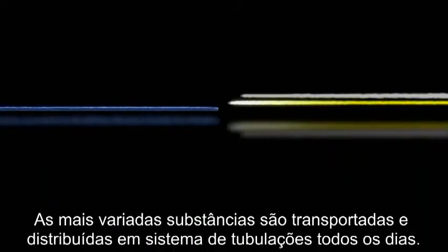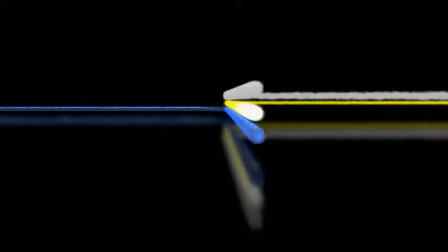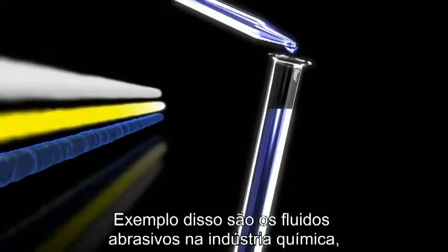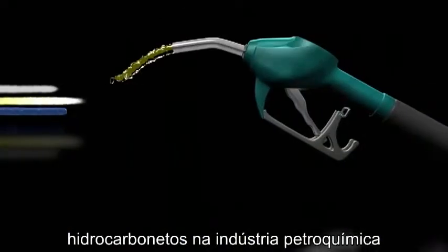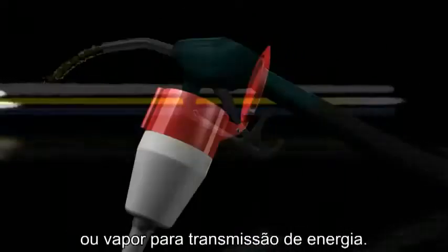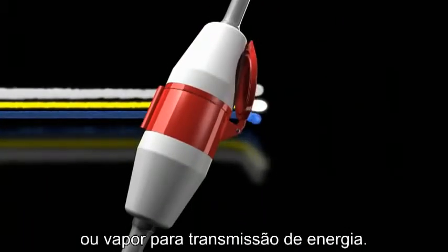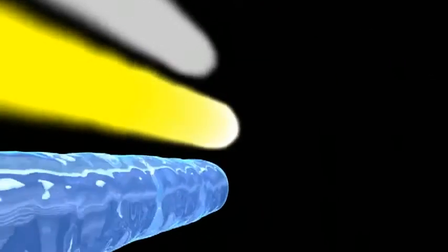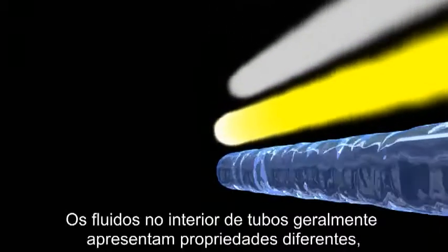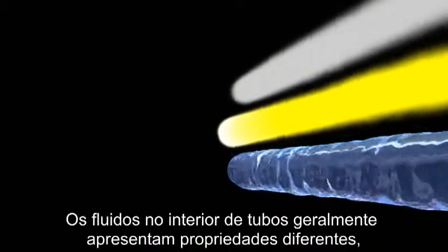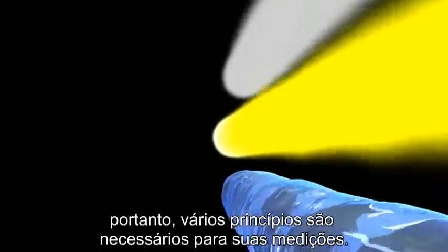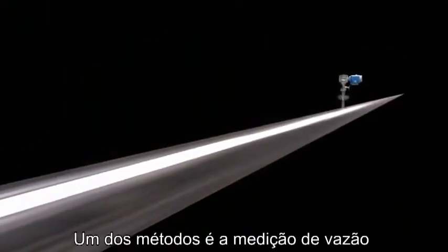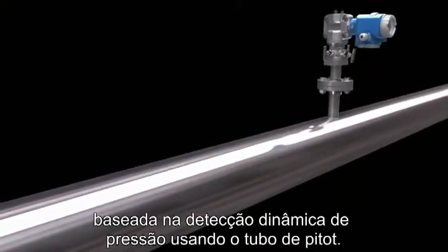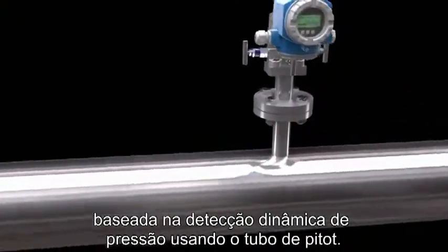The most diverse substances are transported and distributed in piping systems every single day. They can include aggressive fluids in the chemical industry, hydrocarbons in petrochemistry, or steam for energy transmission. The fluids flowing through pipes often have completely different properties. Therefore, different principles are required for their measurement. One principle is flow measurement based on dynamic pressure detection using a pitot tube.